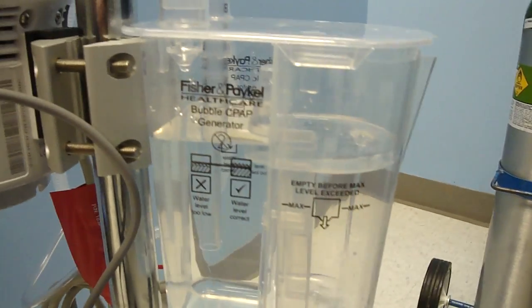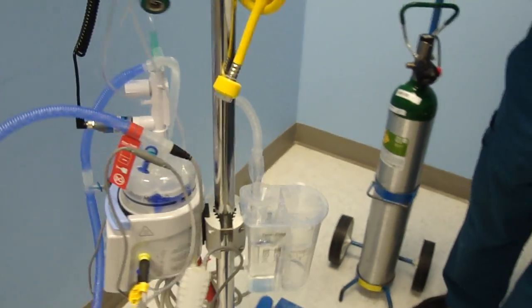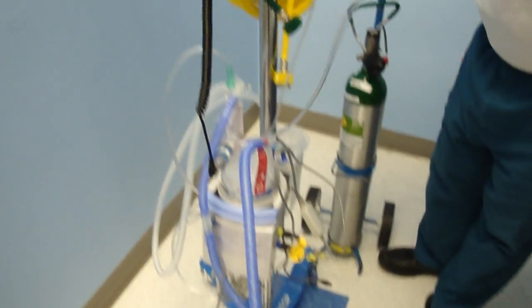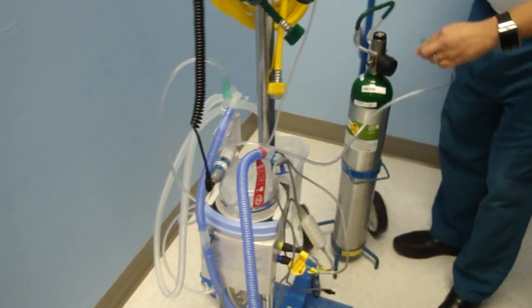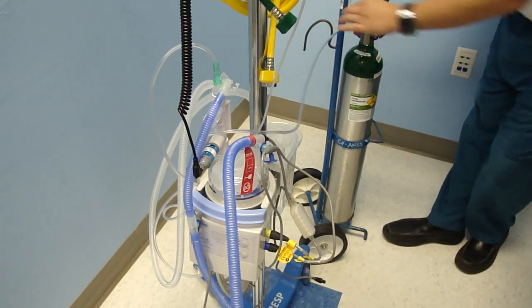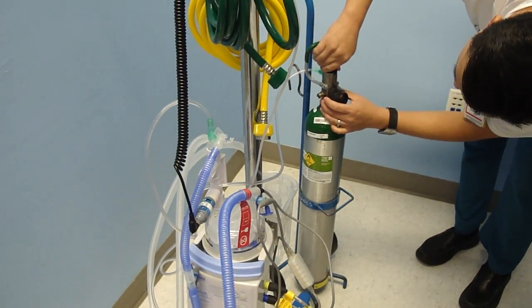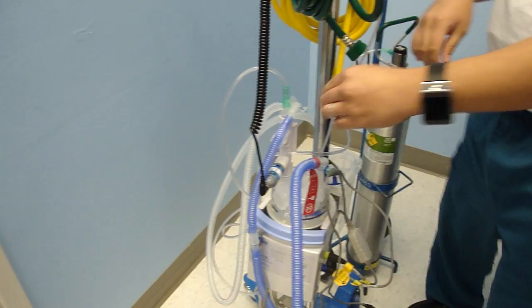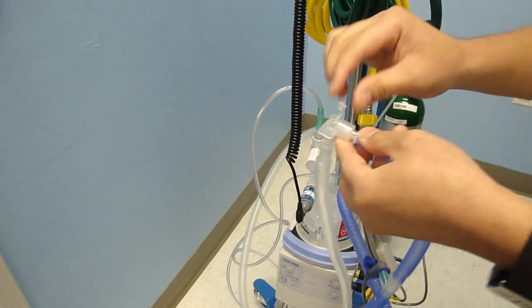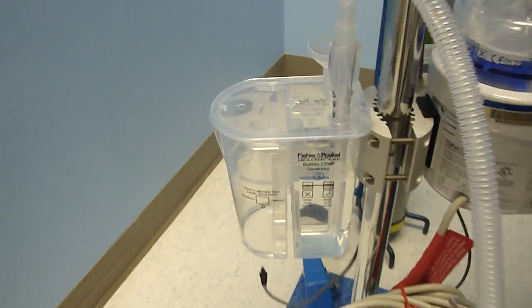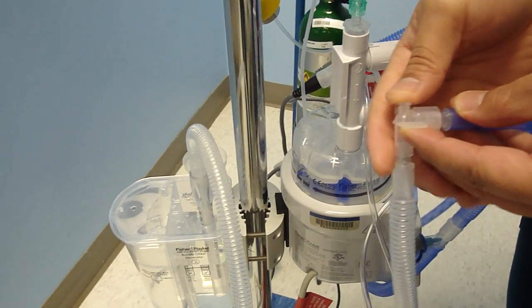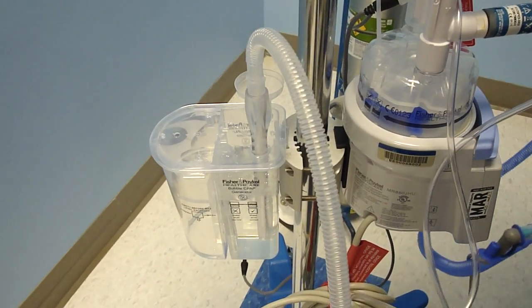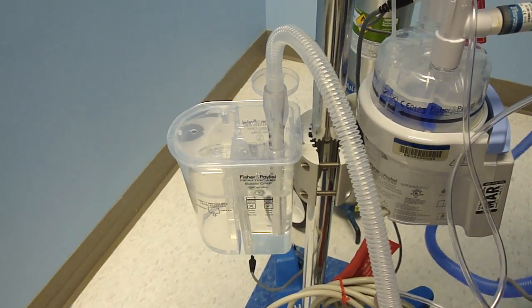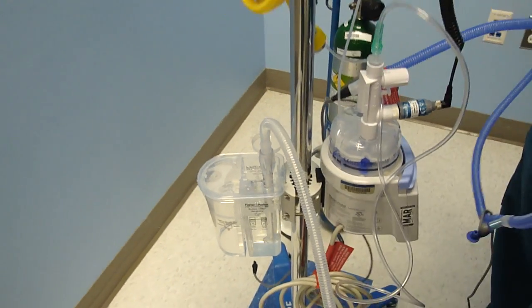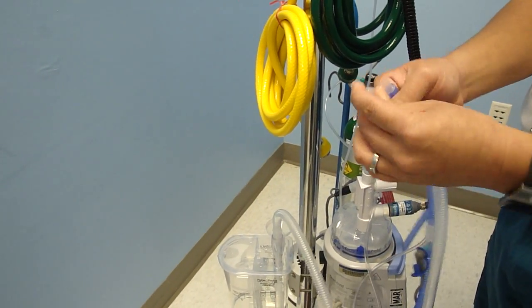Okay, so now I'm going to do a leak test. You set your flow meter at 1 liter, I'm going to use the portable tank. With that elbow that I mentioned before, right now the cap is open, I should not see any bubble in my bubbler. Okay, when I cap, I should see bubble, which tells me that the system is good, no leak in the system. That's it. That's a quick test, and after this, just remove it.